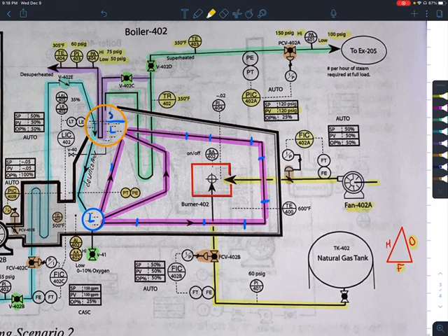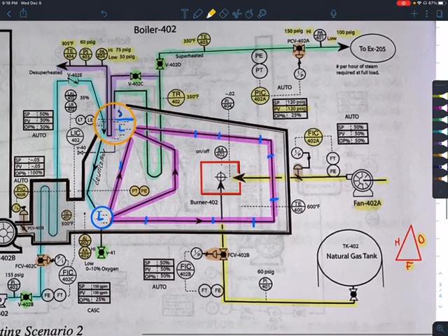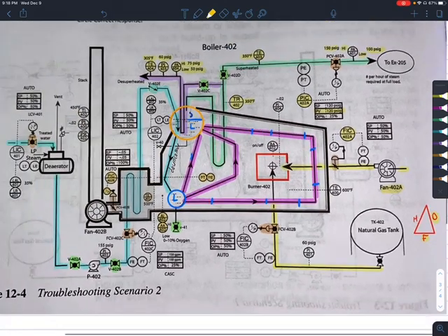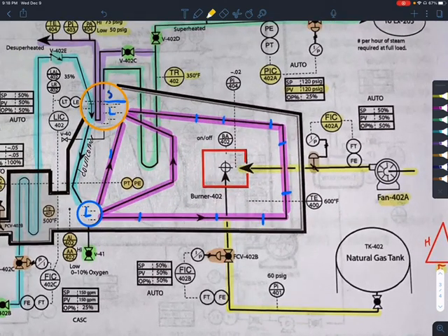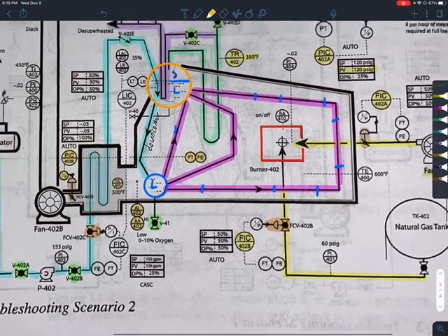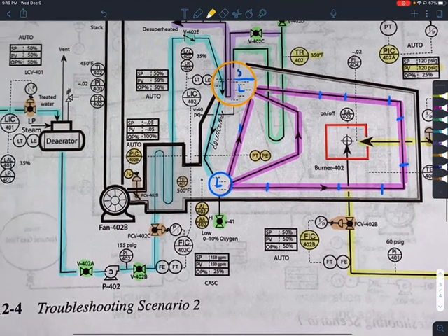Let's say if there's too low oxygen, this fan will kick up. All right. Flow indicator controller will open up the butterfly valve again. I'm pretty sure I already covered that. It also works with FIC for the burner. So that if there's too little flame, it's not because it's hot, it's going to put in more gas, right? So that's the purpose of that. So that's that control loop. Yeah, I'm pretty sure I've covered that.